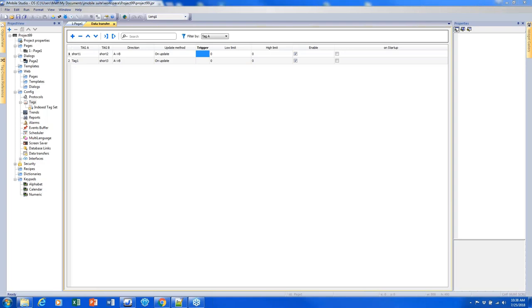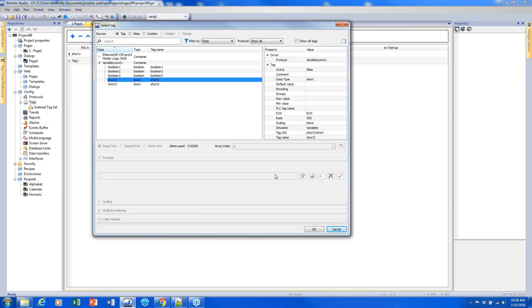Data conversion is actually not available in data transfer jobs — that's why it's grayed out. If you want to do any kind of math on the source or destination tag, you have to do that in the PLC prior to the actual data transfer. Within the data transfer jobs, expressions are grayed out because we assume any math needed has already been applied. Expressions are available when you put a numeric field on the page — you have the ability to add custom expressions or select from a list.